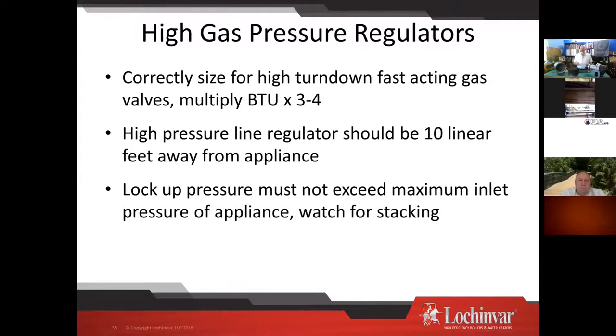Oversizing the gas pressure regulator definitely works better by keeping it from opening a lot — this applies to any new-style boiler with fast-acting gas valves. Going up 3 to 4 times the BTUs is usually only one size increase in a regulator. Make sure you have a bubble-tight lock-up regulator, not an appliance regulator that will eventually bleed pressure through. A lot of issues we run into are regulator-related. Get them at least 10 linear feet away from the appliance, and ideally a regulator per boiler when you have multiple boilers.